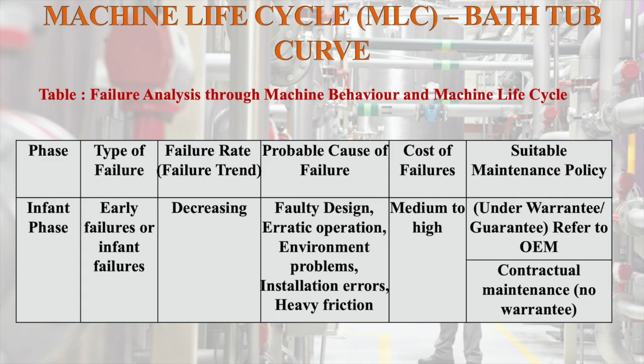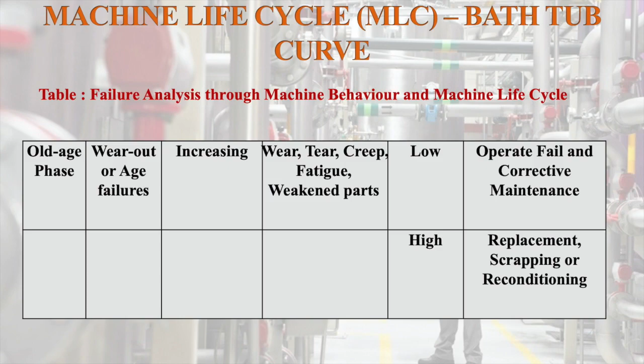Why it happened: faulty design or erratic design operation, and the cost of the failure will be medium or high. So one has to adopt a suitable maintenance policy for such infantile failures: warranties referred to the original equipment manufacturer, or contractual maintenance can be done for this early infant failure phase. If it is the youth phase, breakdown maintenance or preventive maintenance has to be adopted. If it is the old age phase, one has to adopt operate to failure or corrective maintenance when the cost is low, and when the cost is high, replacement, scrapping or reconditioning of the machine. Such types of maintenance methods have to be adopted.